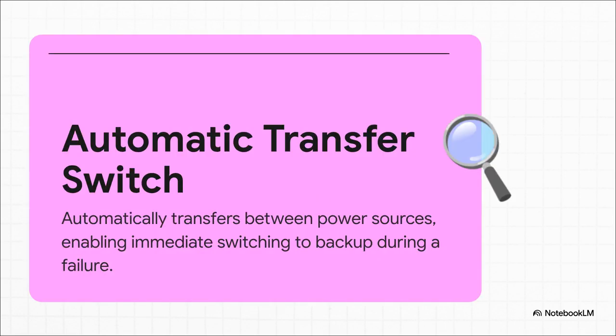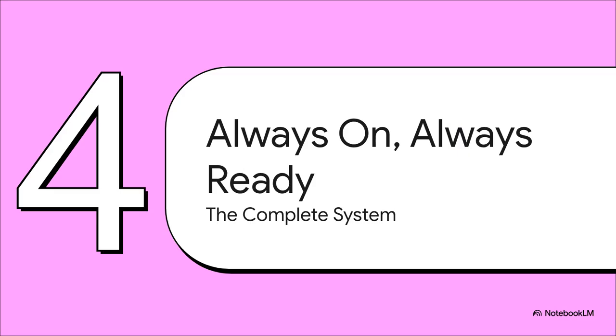So what's making this whole complex dance happen so fast and just flawlessly? Well, the conductor of this whole orchestra is the automatic transfer switch, or ATS. It's like a watchdog, constantly monitoring the quality of the power. The second it senses a problem, it orchestrates that entire handoff between the grid, the UPS, and the generator. All of it, automatically, without a single person needing to even think about flipping a switch. So when you put all of these pieces together, the redundant sources, the instant failover, the layers of protection, you get a system that's designed for one thing and one thing only: absolute reliability.